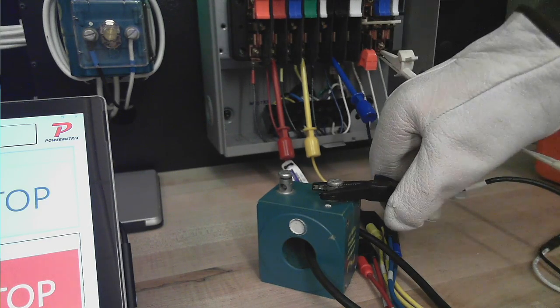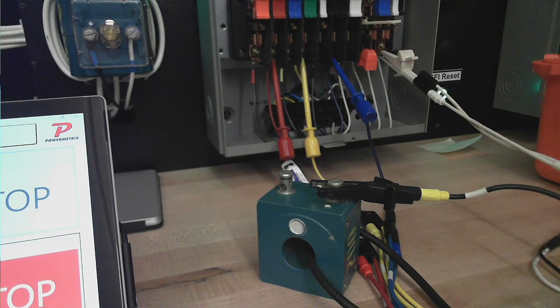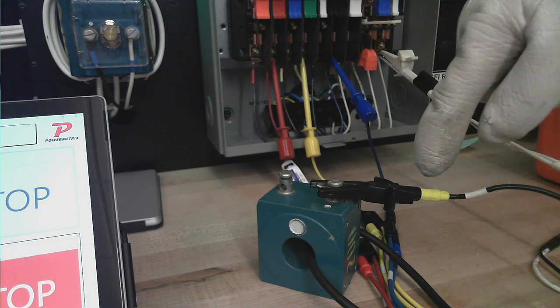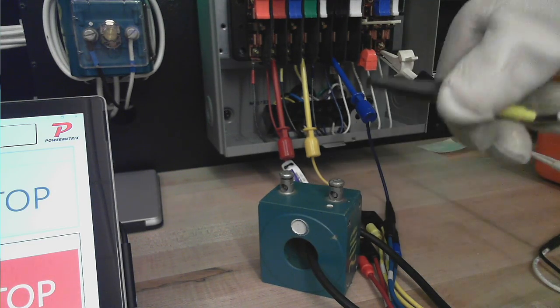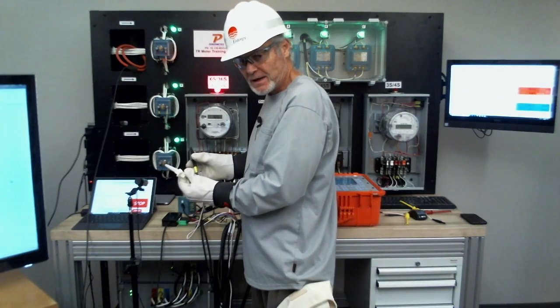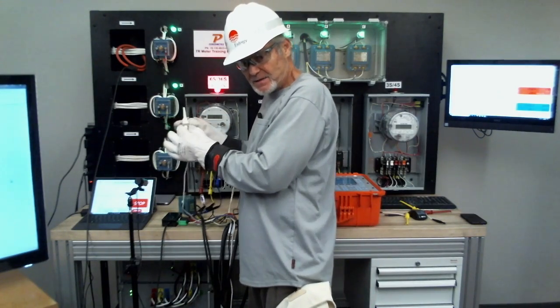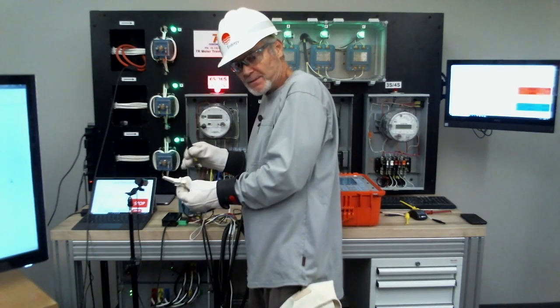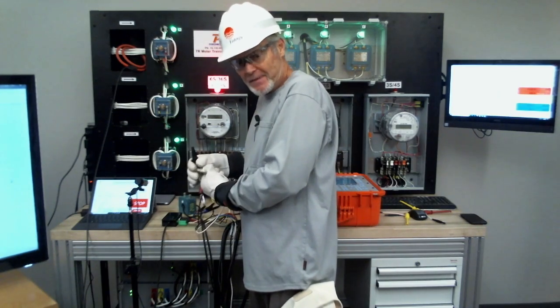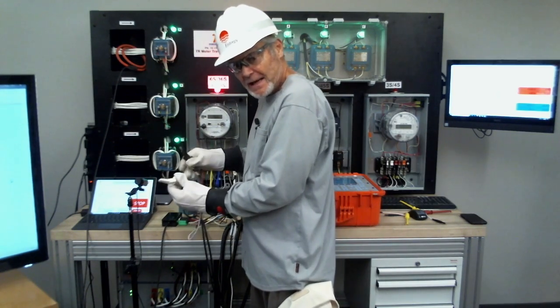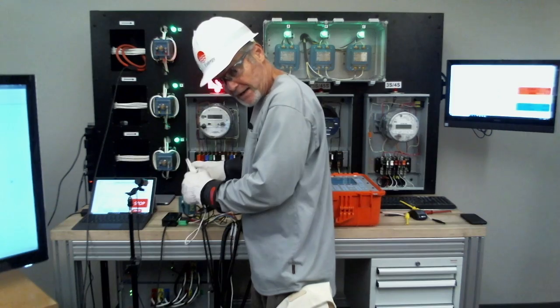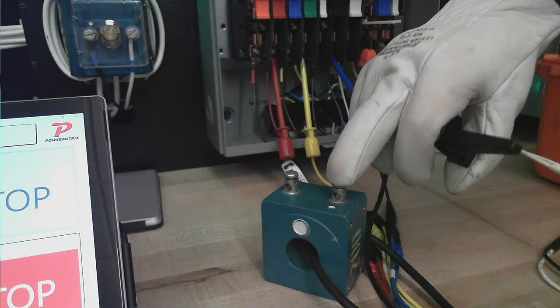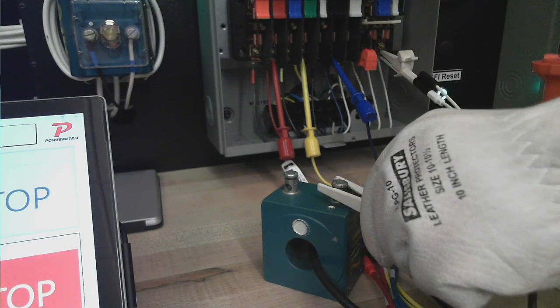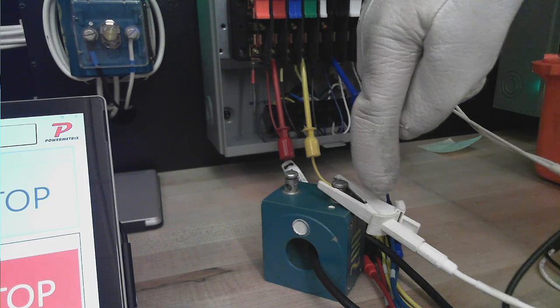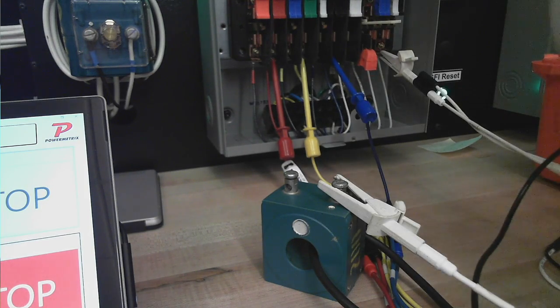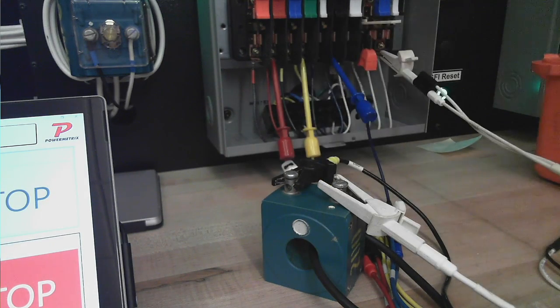They put that black on the dot. Remember, it's in the white, out the black. Right now I'm using these to measure the secondary current. I can't stick a duckbill in there, so I've replaced it with these two alligator clips. To measure it, these two alligator clips are going to act just like a duckbill: in the white, out the black. So if I'm coming out of here, I need to connect my white here because the current comes out of there, goes in the white, and comes back out the black.